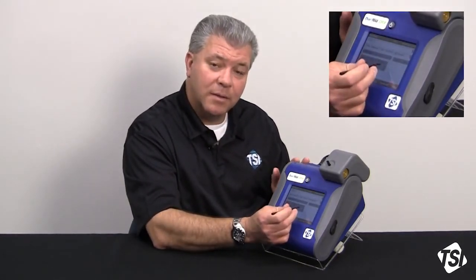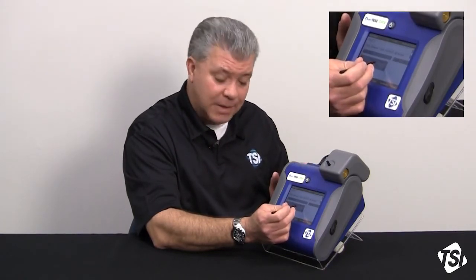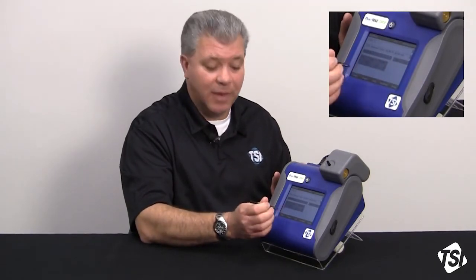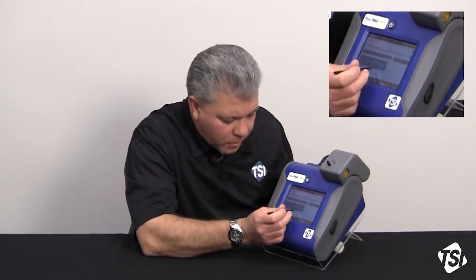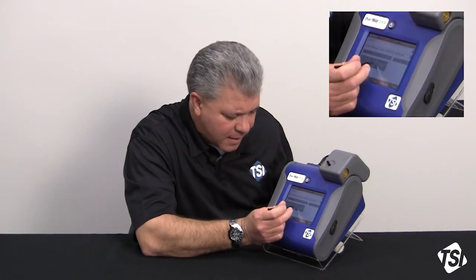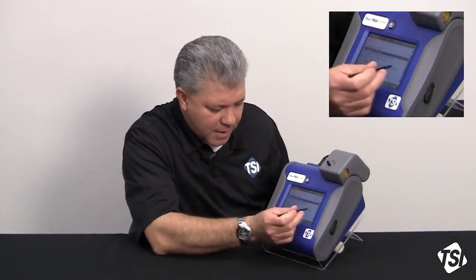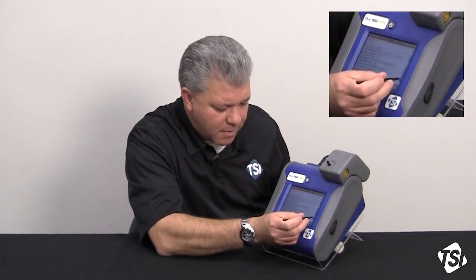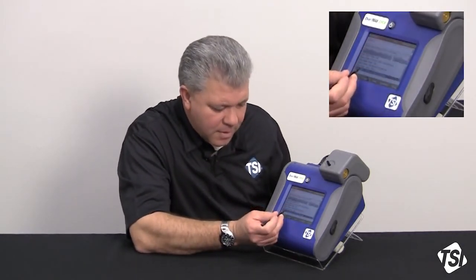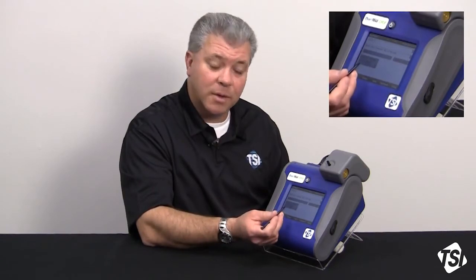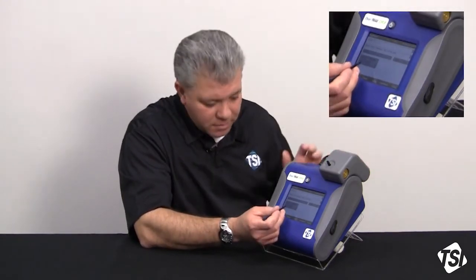Then it's going to reset the logging interval to 2 minutes. Now, I can have more than 2 minutes. I just can't have less. So it wants me to set that. Setting that, I'm going to scroll back down, and now what is the frequency or the timing that I want to input into the instrument so that it zeros during sampling?